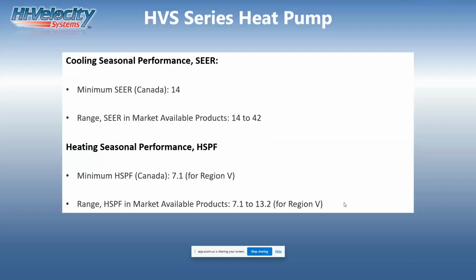Heat pumps, cooling season performance, SEER rating should be at 14 SEER. That's a rating that the Canada government rates these. That's the minimum SEER on a cooling. And you can get them from 14 to 42 SEER rating. Heating season performance, that is HSPF. The minimum in the Canada government is 7.1. So, and again, that's up to 7 to 13 rating on the heating side of a heat pump.